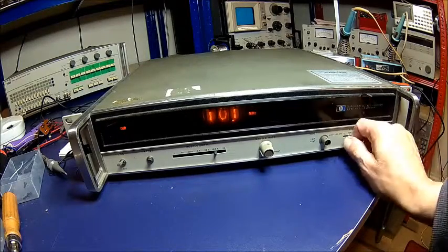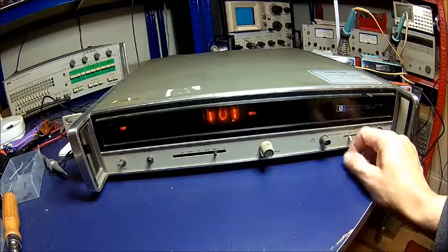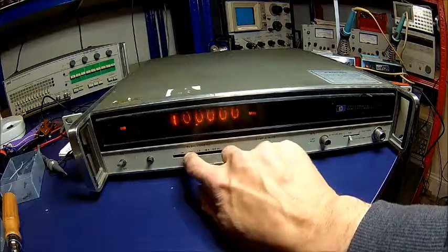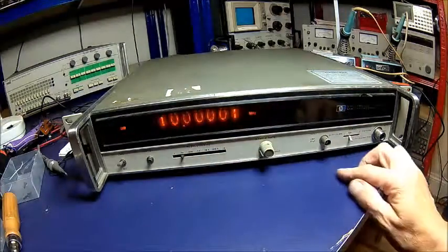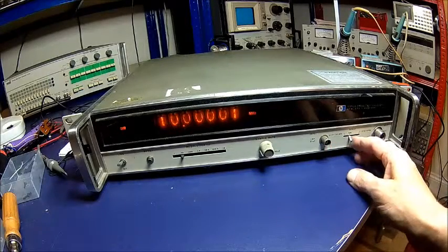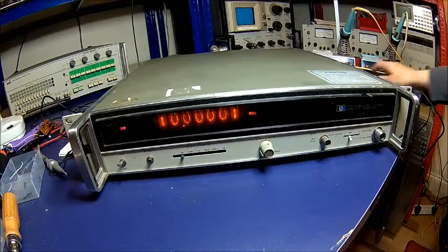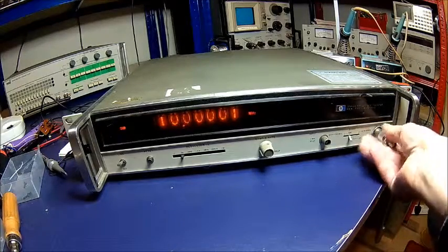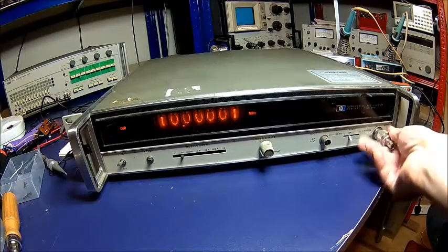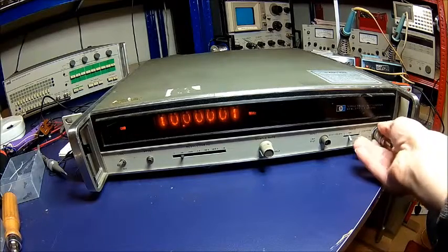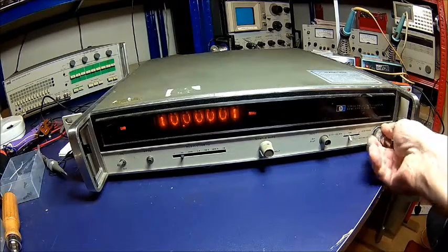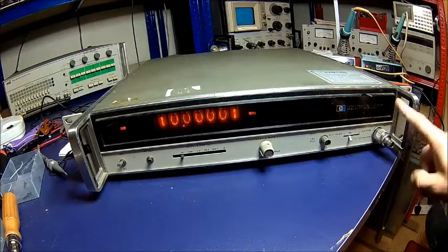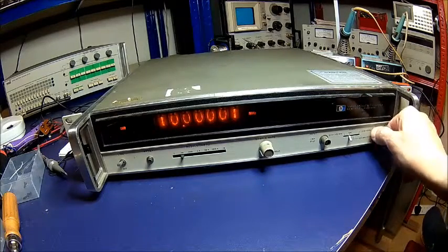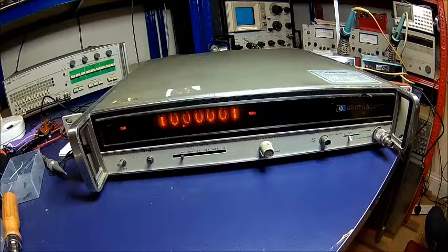So let's see what it does. It's reading something here. At least the self-check is working. Let's feed some signal in here. These counters usually suffer from a fried high frequency input. It doesn't like a lot of power. It's only 7 dBm maximum. There's a sticker here as well which says that, but some people don't care.